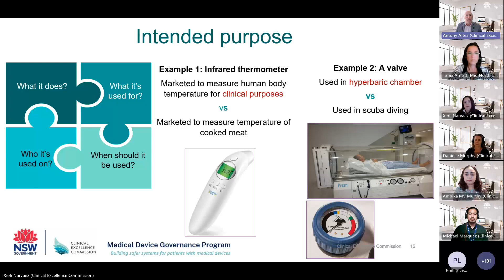Now, let me give you two scenarios. Let's say if devices are created from scratch using one or more non-ARTG listed materials or components, then the final product must be included in the ARTG. I'll be explaining this in a bit more detail in the next slide. And also, if you are importing a medical device from overseas, then you become a sponsor and must include the device in the ARTG. Now, on the other hand, if pre-manufactured materials or components in the ARTG are assembled, modified, or adapted without changing the intended purpose of the device, then no additional ARTG inclusion is required. Now, this means then that healthcare workers have no extra responsibilities in this situation.